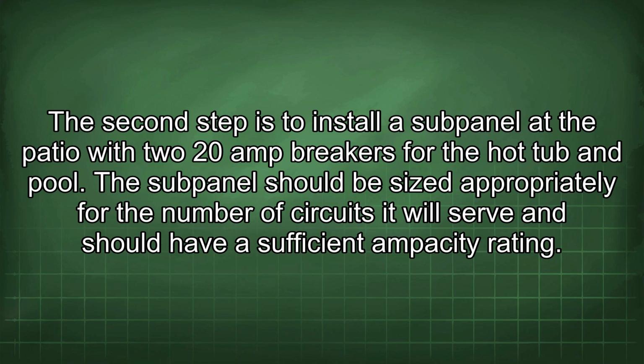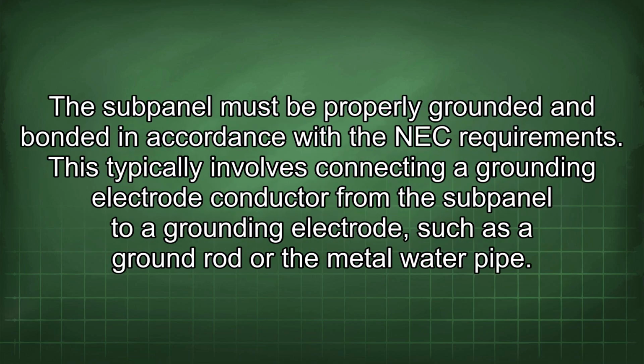The subpanel should be sized appropriately for the number of circuits it will serve and should have a sufficient ampacity rating. The subpanel must be properly grounded and bonded in accordance with the NEC requirements. This typically involves connecting a grounding electrode conductor from the subpanel to a grounding electrode, such as a ground rod or the metal water pipe.